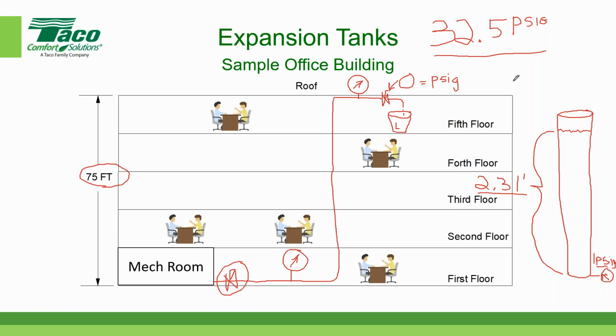Taco Tuesday, that's right. So yes, the pressure gauge at the top of this system will read 0 PSIG. Now, in a hydronic system, I don't want 0 pounds at the top. I want something different than that. Anybody want to take a guess as to what pressure I want at the top? We've got answers of 5, 4, 7.5, or 15. Most engineers will say they want somewhere between 5 and 10 pounds per square inch gauge at the top of the building. For today's discussion, to make the arithmetic simple, I'm going to go halfway between those two and say I would like to have 7.5 PSIG at the top of my piping system.